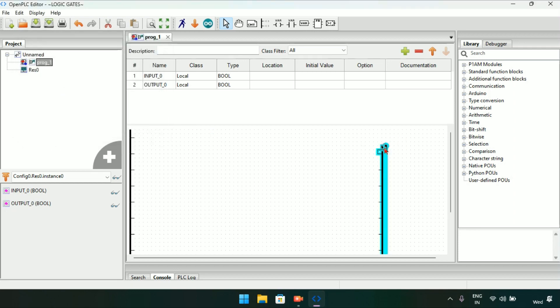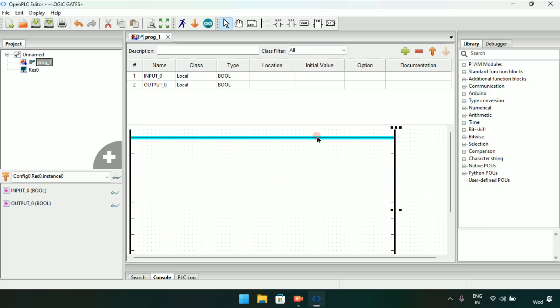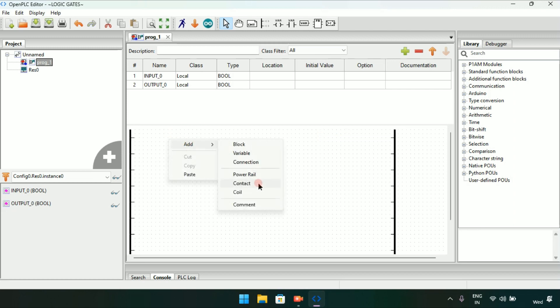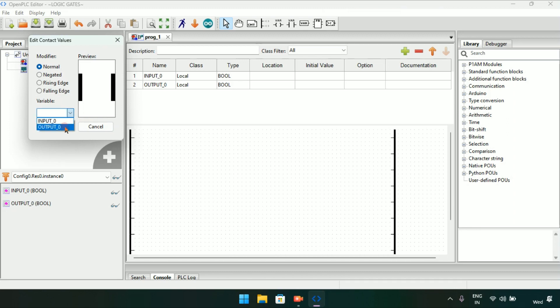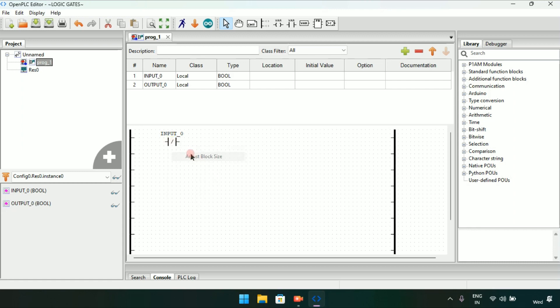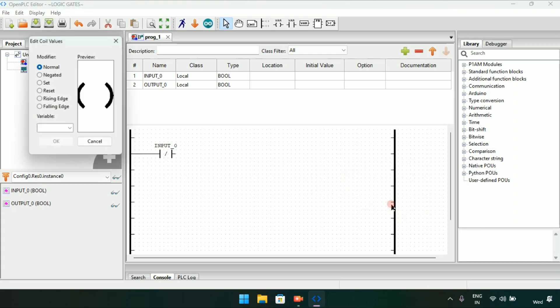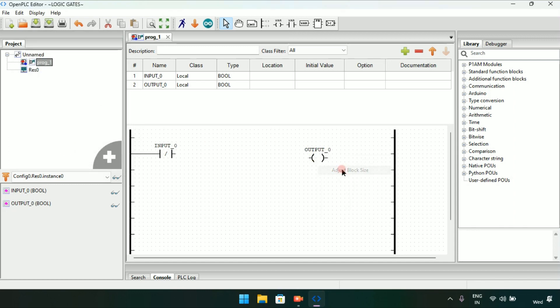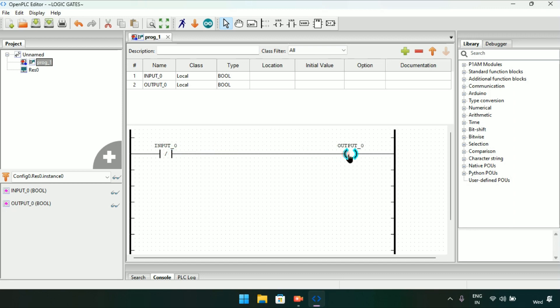I will align the power rails, then add an input. I will modify the input as negated, which is a normally closed contact, and adjust the block size. Now I will join the pins and add an output, adjust the block size of the output, join the pins together, and then start the simulation.